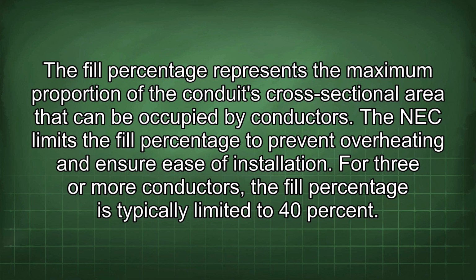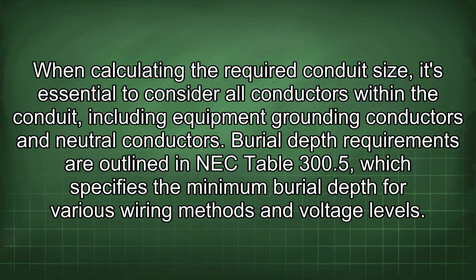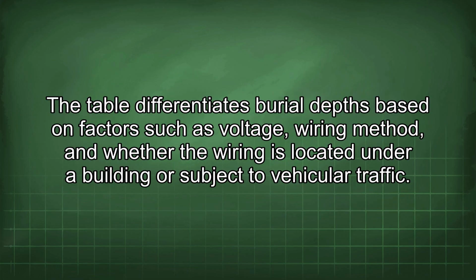For 3 or more conductors, the fill percentage is typically limited to 40%. When calculating the required conduit size, it's essential to consider all conductors within the conduit, including equipment grounding conductors and neutral conductors. Burial depth requirements are outlined in NEC Table 300.5, which specifies the minimum burial depth for various wiring methods and voltage levels. The table differentiates burial depths based on factors such as voltage, wiring method, and whether the wiring is located under a building or subject to vehicular traffic.